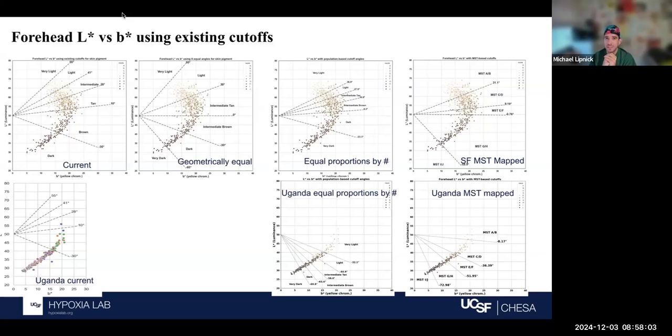But to play the extreme here, let's say that we only see pulse oximeter bias at ITA less than -80. Would we propose that the only change to the current ITA bins be to add a -80? I don't think so.